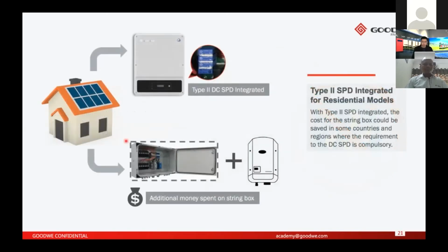The next one is about surge protection. Right now, for some of our residential models like the MS, we are already able to integrate a Type 2 DC-SPD at the DC side. In some regions in India, if a DC-SPD is required on the inverter and you don't have it, you may need to install a string box or DC combiner box to have this additional safety device. So if you choose our inverters, you can save the cost spent on the string box.